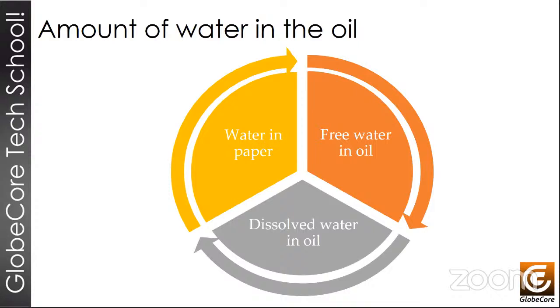So water in the transformer is one of the elements that we really need to keep track of and monitor. However, it's one of the most difficult characteristics to control. There are several processes by which a transformer generates moisture, and there are various parameters that will all be related to moisture, and they will affect all our attempts to keep the transformer dry.